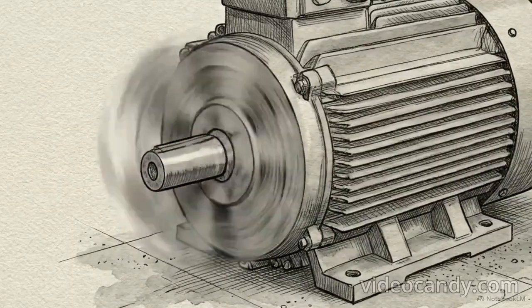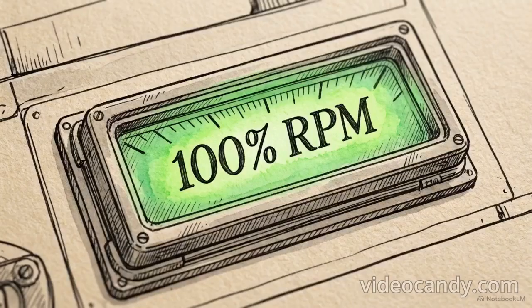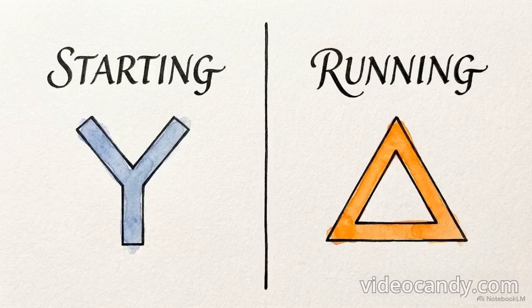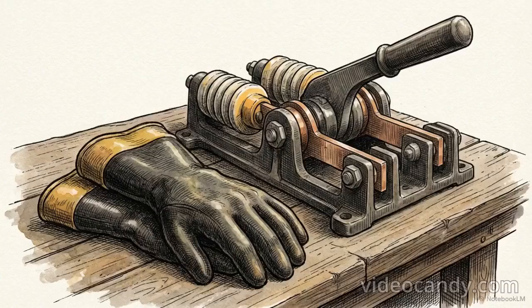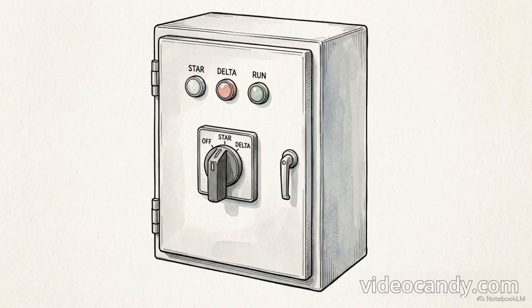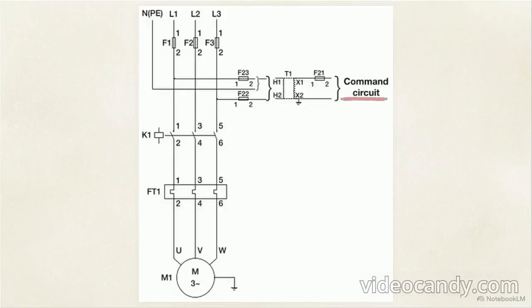Operating at 58% of the voltage, the star phase gives way to the second state, delta. With 100% of the voltage restored to the coils, the magnetic field reaches maximum density, allowing the motor to generate its full rated torque and finally achieve its maximum running speed. The star-delta sequence isolates starting from running. It provides a protected, low-current acceleration phase, followed by an immediate physical reconfiguration to achieve full power operation. Executing this transition manually with high voltage lines is dangerous and imprecise.